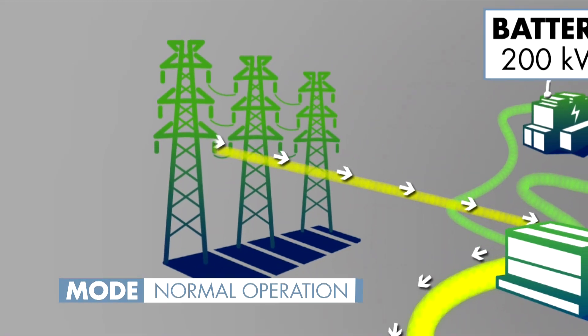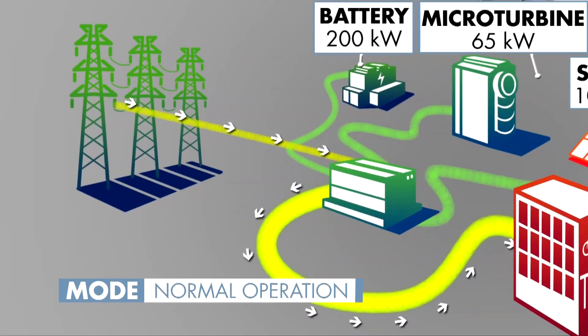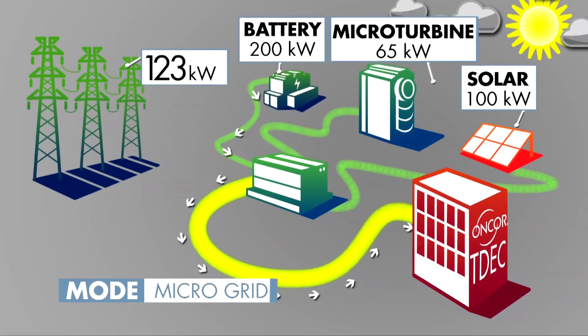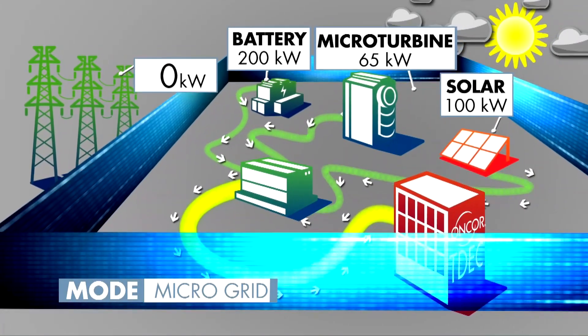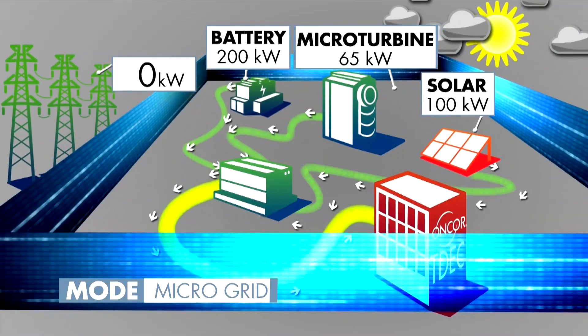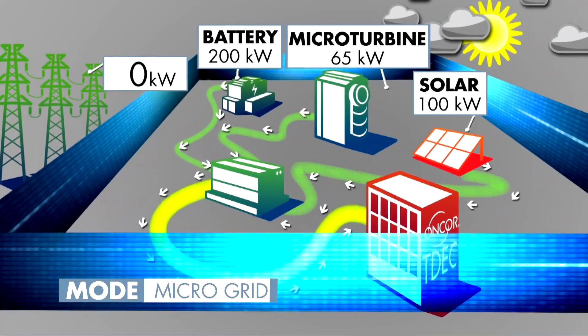This campus is divided into four zones, and each of these zones is itself a microgrid. These grids enable Oncor to disconnect from the utility source and operate nearly indefinitely, while favoring the renewable generating sources and balancing the load between all of the distributed generation based on economic returns available at the time.